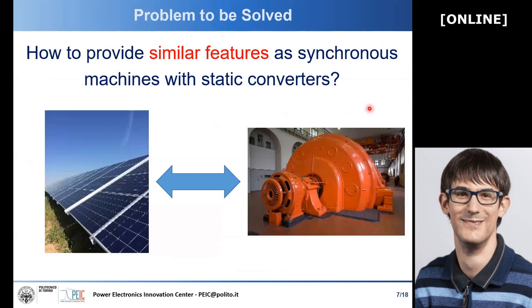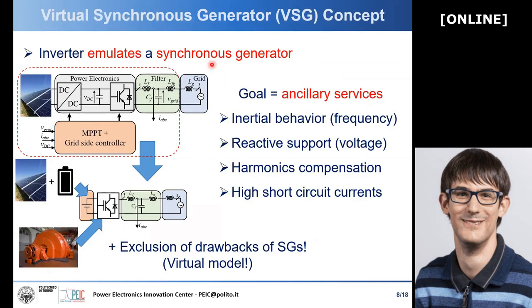So how can we provide similar features as synchronous machines but using static converters and, for example, solar panels? Here comes the concept of the virtual synchronous generator. Basically, we want to make a power converter behave as a synchronous machine. This way, we can provide the so-called ancillary services, which can help guarantee power quality.